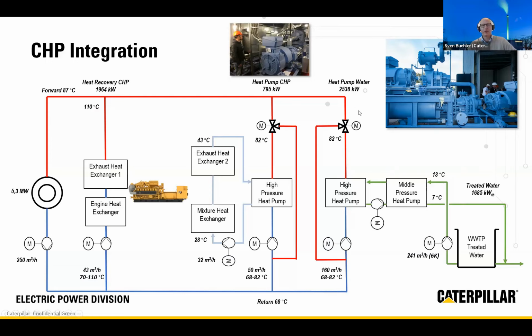So this whole integration helped to really drastically improve the total efficiency of the system. A 2 megawatt G3516, if you consider the low heating value and ISO condition, consumes around 4.5 megawatt hour of energy as gas. And thanks to the two heat pumps, we are able to supply over 5.3 megawatt of heat, and of course 2 megawatt of electricity, which is partly used for supplying the heat pumps.